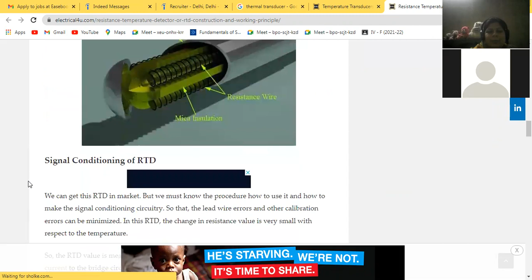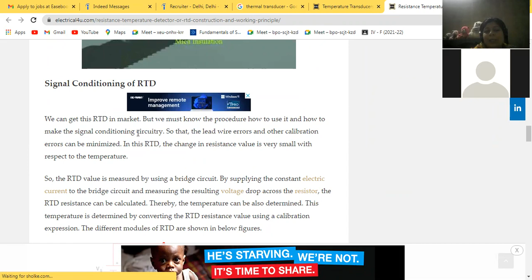Now signal conditioning through RTDs. We can get an RTD in the market, but we must know the procedure, how to use it, and how to make the signal conditioning circuit, so that the lead wire errors and other calibration errors can be minimized. In this RTD, the change in resistance value is very small with respect to the temperature. So the RTD value is measured by using a bridge circuit. By supplying a constant electric current to the bridge circuit and measuring the resulting voltage drop across the resistor, the RTD resistance can be calculated. Thereby, the temperature can also be determined. This temperature is determined by converting the RTD resistance value using a calibration expression.